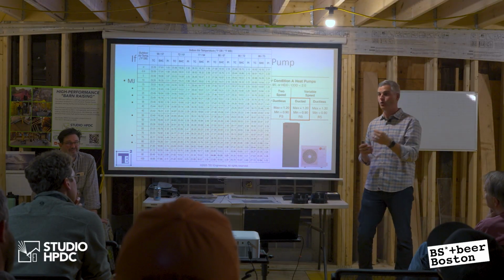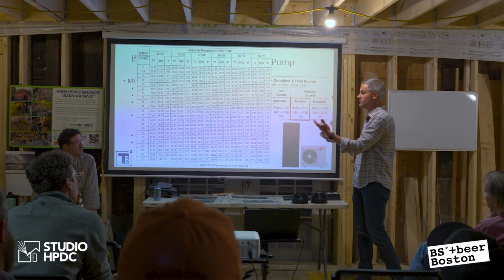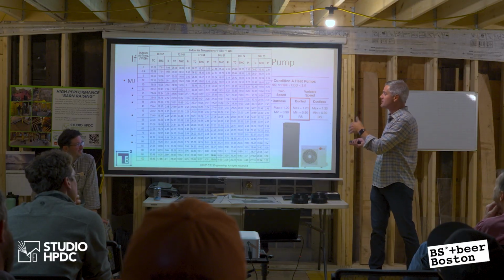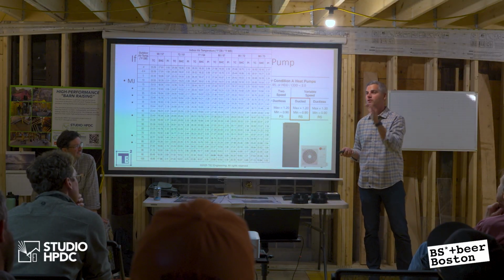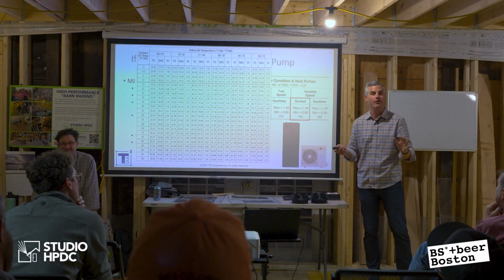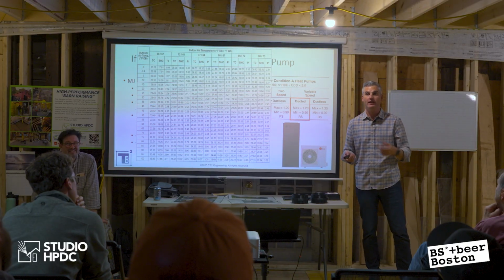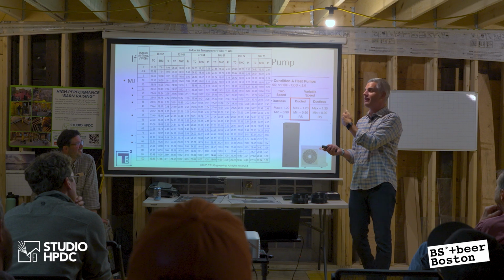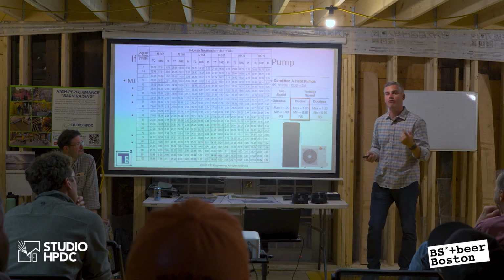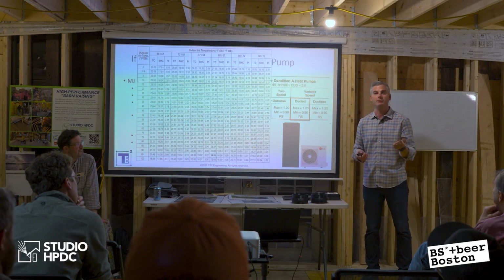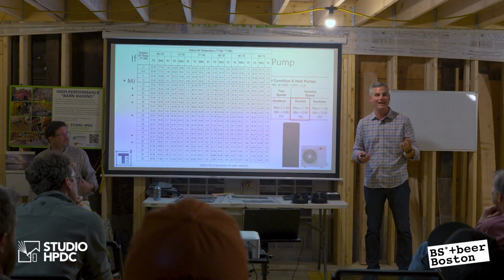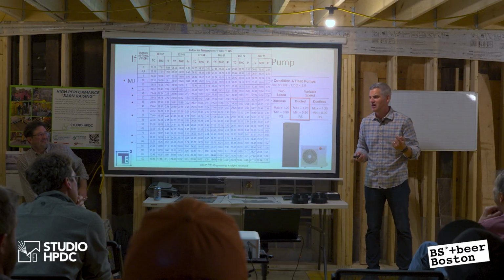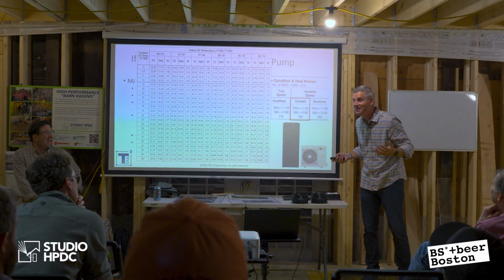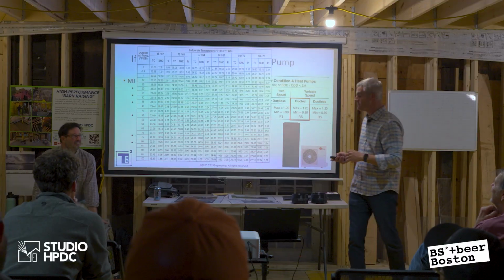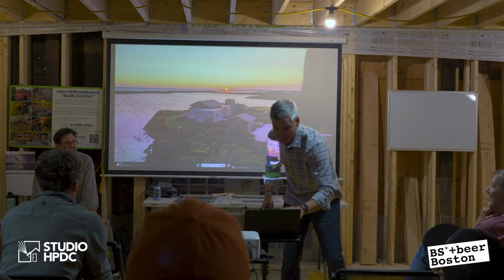So these heating and cooling systems that are now offered with ducted mini splits and VRF strategies, the problem is that they're becoming terminal cooling units for sensible only. They're not doing any moisture extraction. Right? Yeah. And so we have a job where I did the math out. When it runs at a 0.94 sensible heat ratio, it removes 1.1 pints per day. Like, are you freaking kidding me? Yeah, so the myth that we have dehumidification when we have a cooling load is just blown apart.